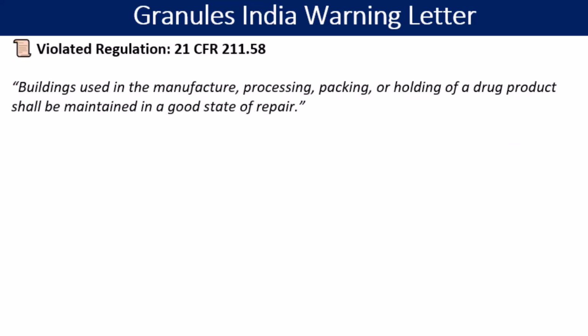The specific regulation violated here is 21 CFR 211.58, which clearly states that manufacturing buildings must be maintained in a good state of repair. This is not just about aesthetics or routine cleaning; it is about ensuring the building, its structure, and environment are fit for production of safe and effective medicines. The moment you allow cracks, leaks, or pest ingress, you are exposing your product to avoidable quality risk.